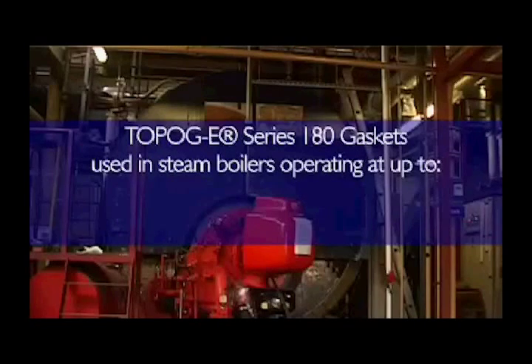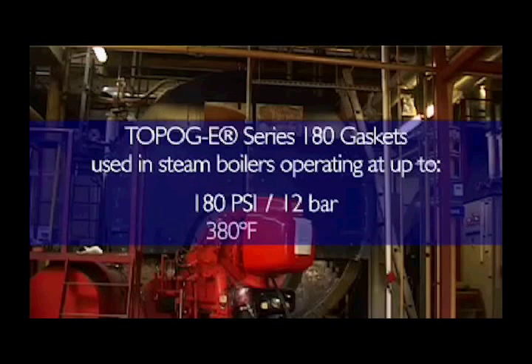Most TOPOG-E series 180 gaskets are used in steam boilers operating at up to 180 psi or 12 bar and 380 degrees Fahrenheit or 193 degrees Celsius. For higher pressures and temperatures, TOPOG-E series 2000 gaskets are recommended.